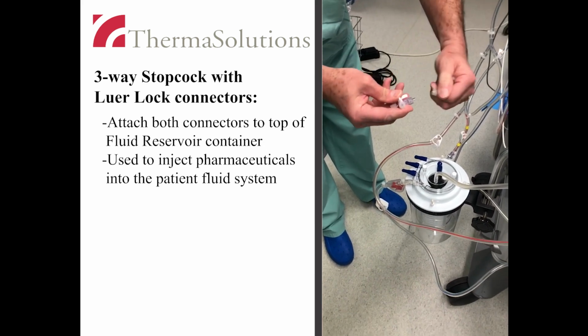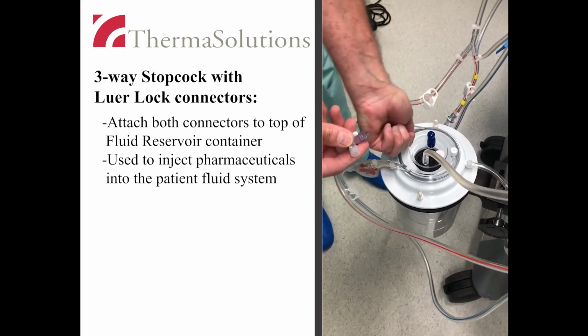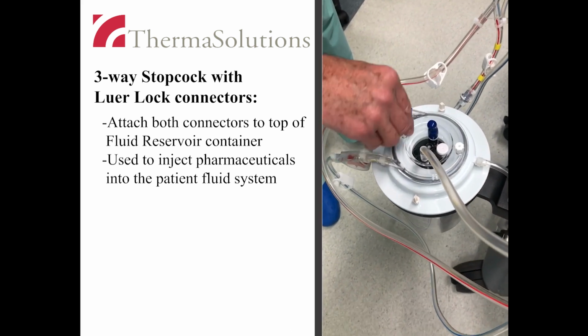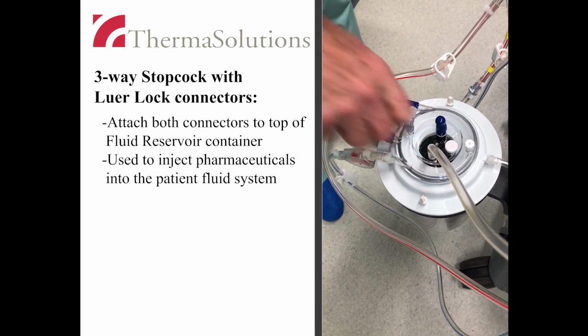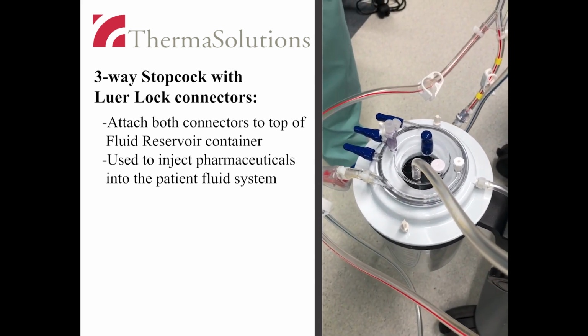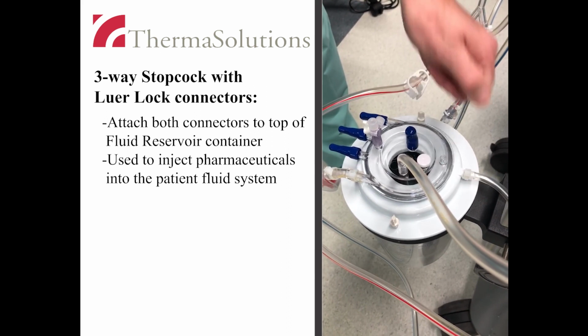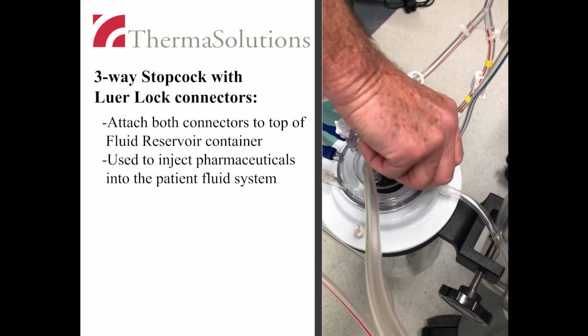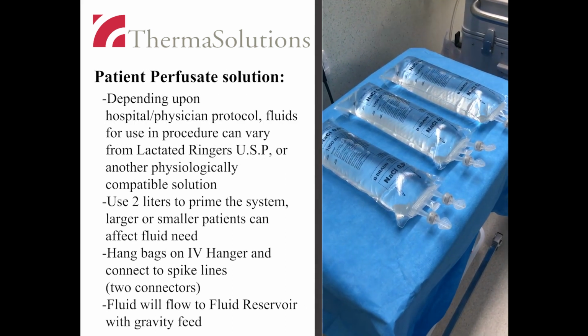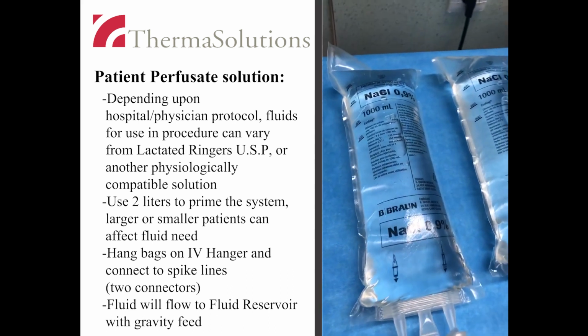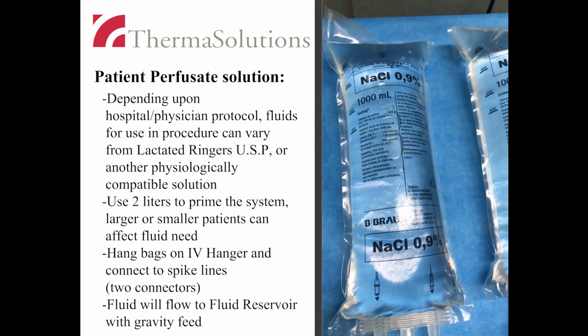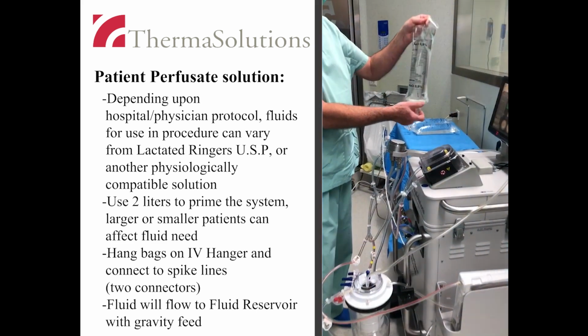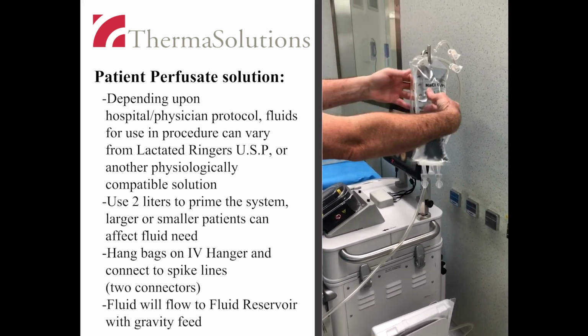The three-way stopcock with luer lock connectors are attached to the top of the fluid reservoir. The stopcocks can be used to inject pharmaceuticals into the patient fluid system. The patient perfusate solution will be lactated Ringer's USP or another physiologically compatible solution as determined by the physician. Prime the system with 2 liters. Total volume required for the procedure can vary for larger or smaller patients. Place the solution on the IV hanger rod and connect the solution to the filled tubing.